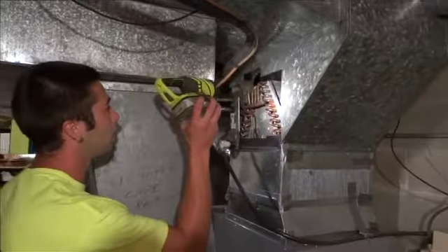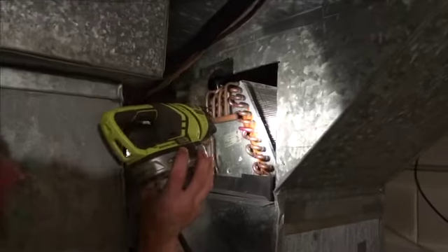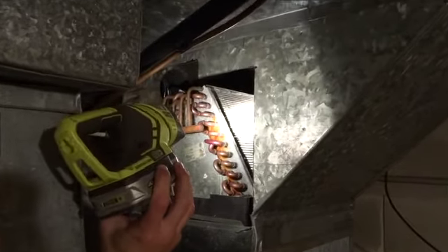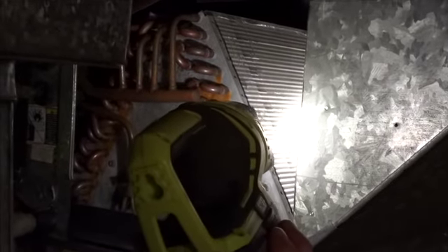See inside here, it's relatively good. Usually you can start telling when they get dirt and dust built up on them, then that's usually a bad sign. It'll really cut down on your airflow. So we'll spray this down just like we did the air conditioner outside.